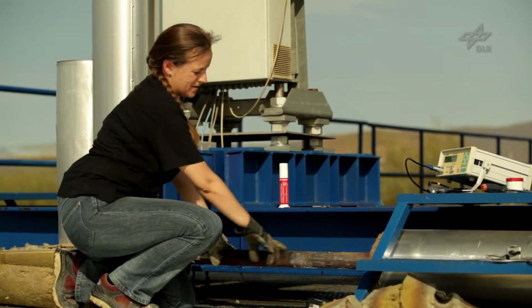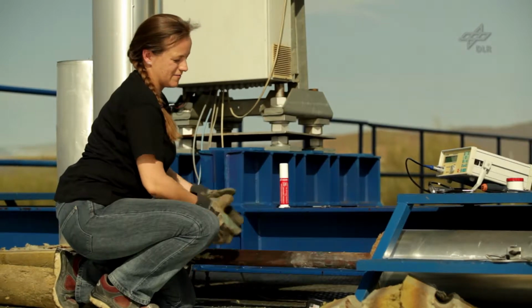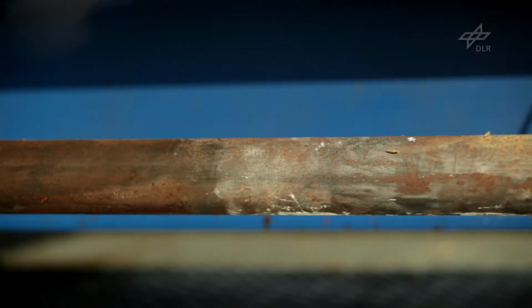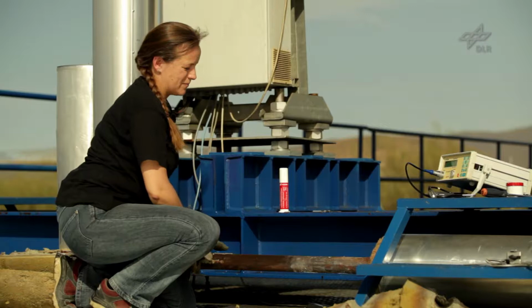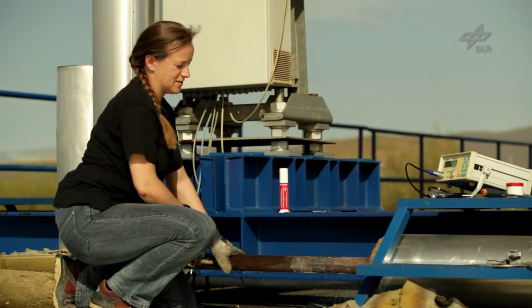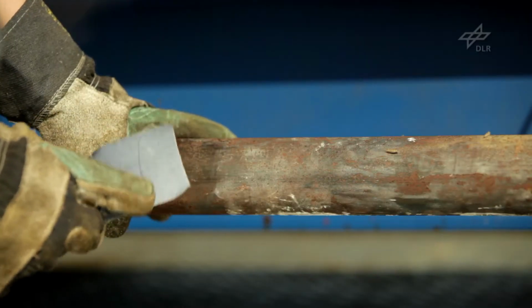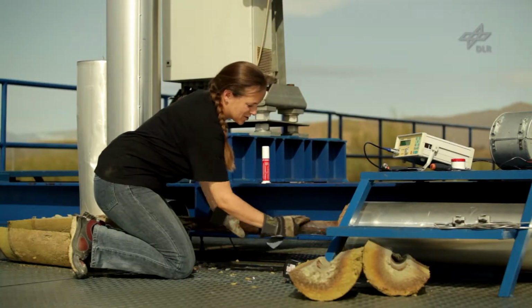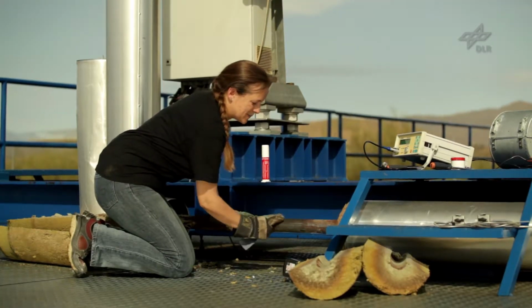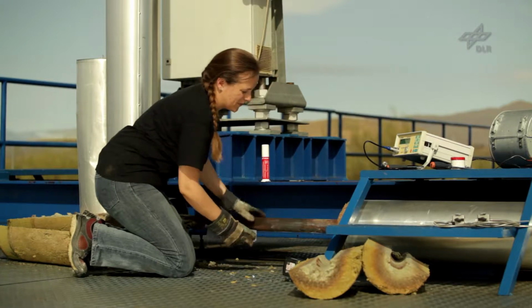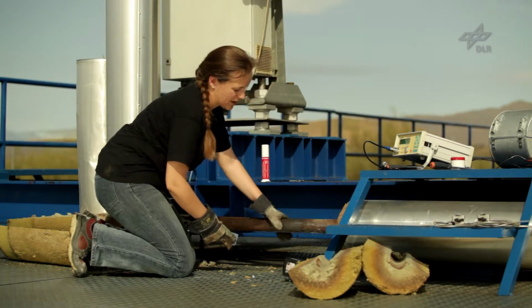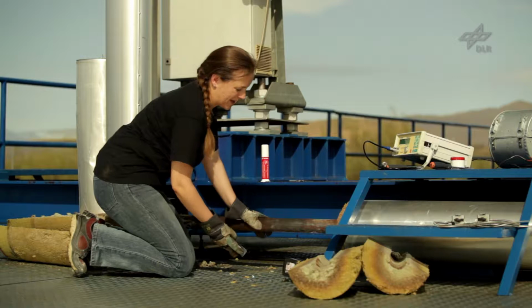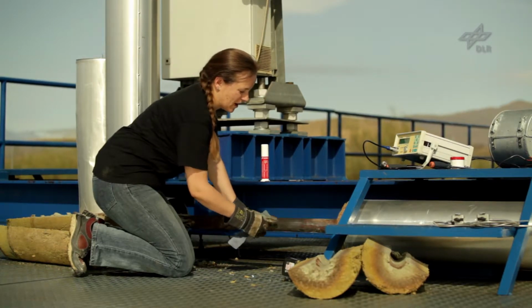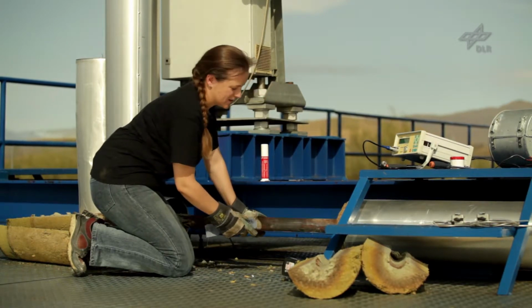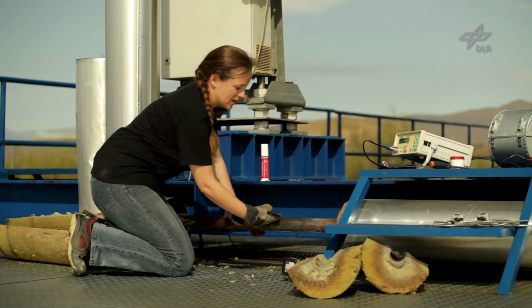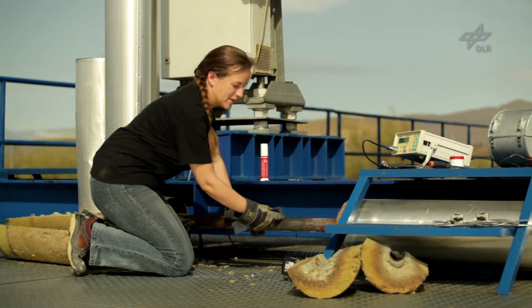So there we are with just the metal piping left. In order to proceed, we will need to clean the piping from dust and rust and any particles. For ultrasonic flow measurements, it is particularly important that the pipe surface is smooth and free of any dust, paint, rust or other obstructions to the signals, so that the acoustic coupling of the signals to the pipe is optimum.